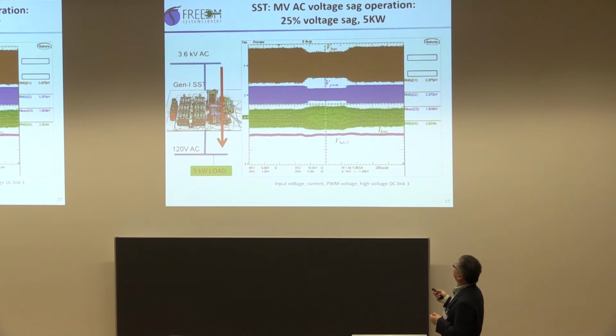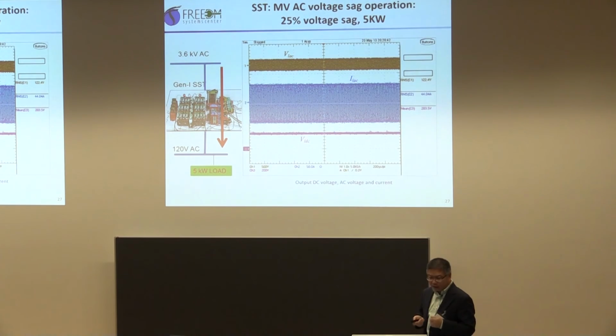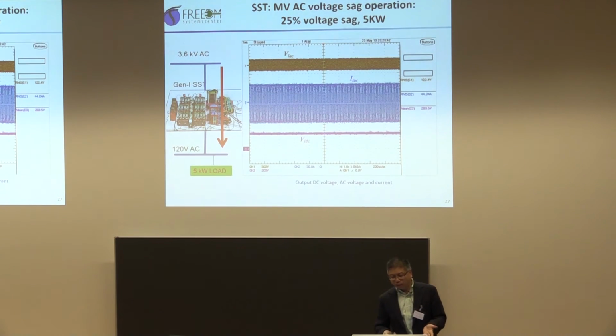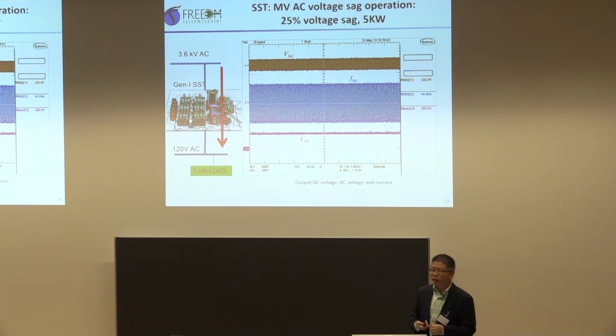This capability is a free product of this technology. We can design it to mitigate certain levels of voltage sag. Here's a 25% sag on the high voltage side, and on the low voltage side we don't see any sag at all. This has economic value. When you talk about the cost of a new technology, you also need to look at the new benefits and capabilities the solution provides.